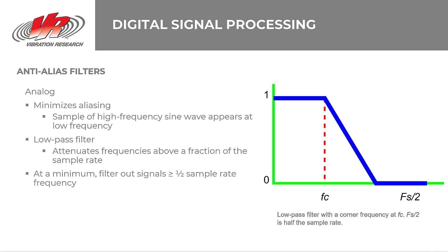Vibration control hardware makes use of filtering to improve control, and most controllers apply filters during digital signal processing. Nearly all instrumentation in a vibration testing lab is digital, but real-world signals are analog. Vibration control hardware digitizes analog signals from the shaker table for processing, and then converts the signals back to analog before outputting the drive.